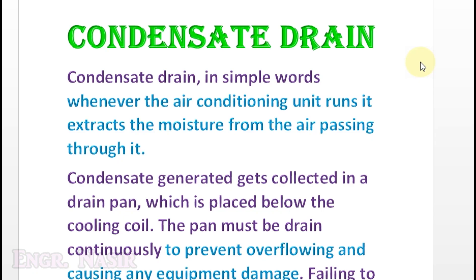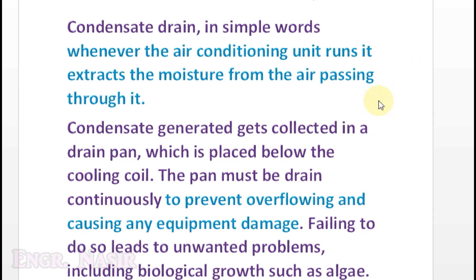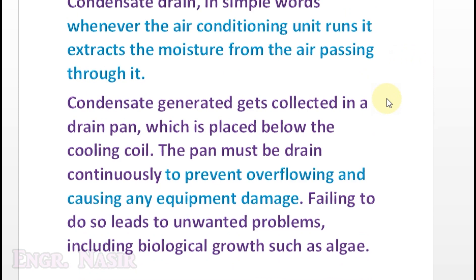Before starting the calculation, let us see what condensate drain is. In simple words, whenever an air conditioning unit runs it extracts moisture from the air passing through it. The condensate generated is collected in a drain pan placed below the cooling coil. This pan must be drained continuously to prevent overflow and equipment damage.